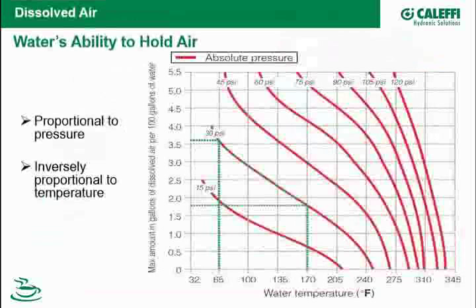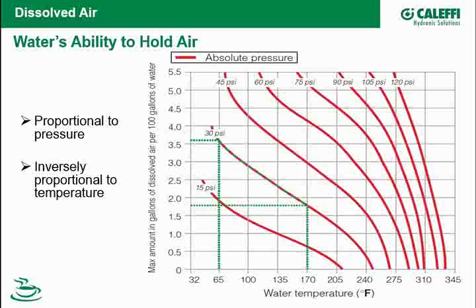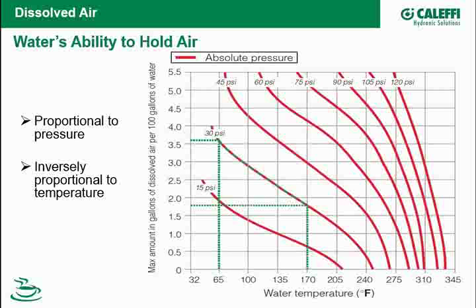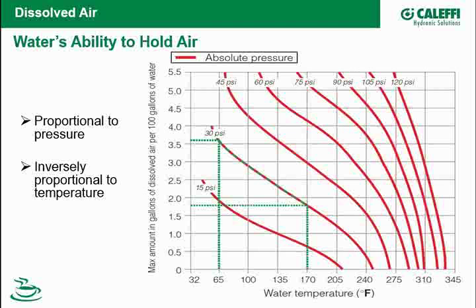Here's another great chart out of Idronics 15. It looks at the relationship between solubility, pressure, and temperature. The scale on the right is maximum solubility in gallons of dissolved air per 100 gallons of water; across the bottom is temperature; and the red curves are all based on pressure. When I look at pressure: the higher the pressure, the more air I can hold in solution. When I look at temperature: it's inverse — the higher the temperature, the less air I can hold in solution.